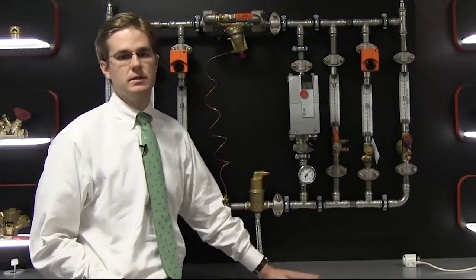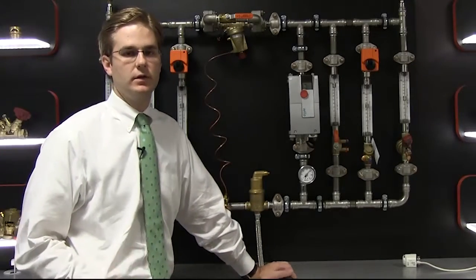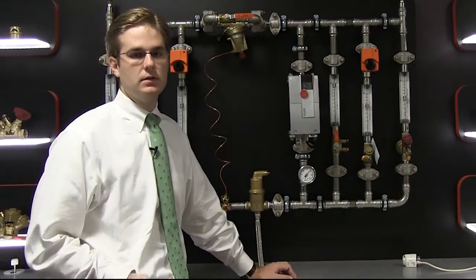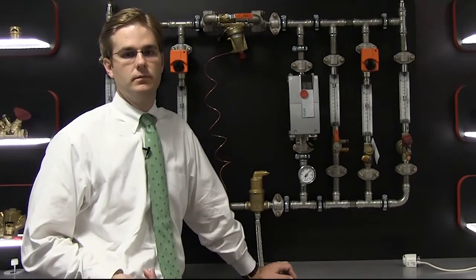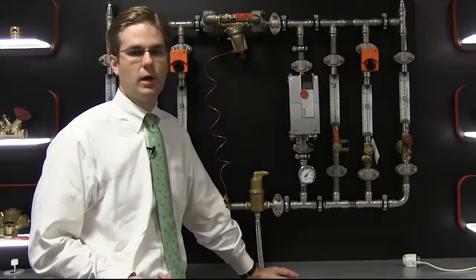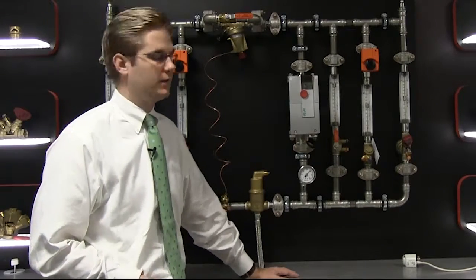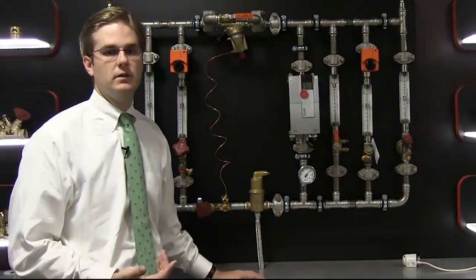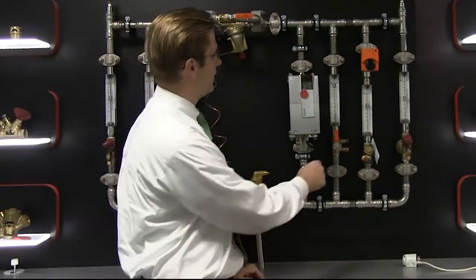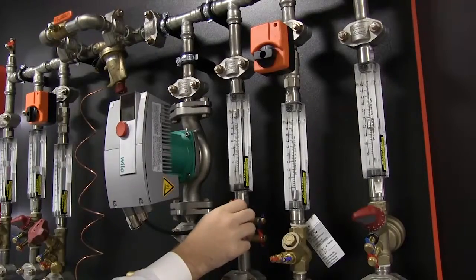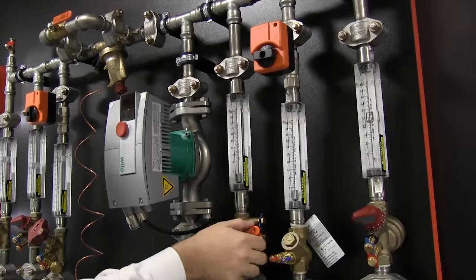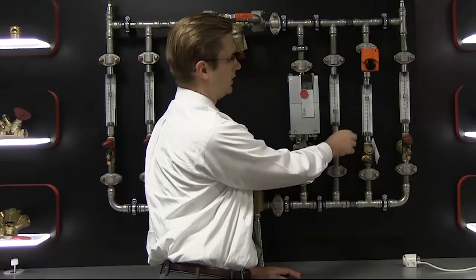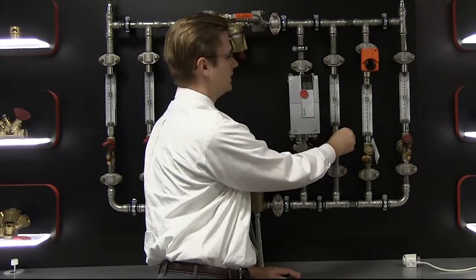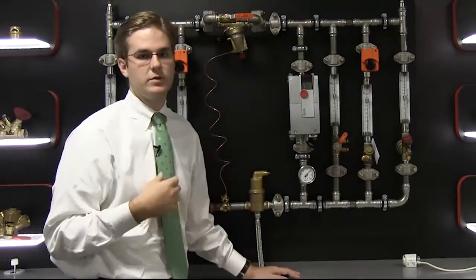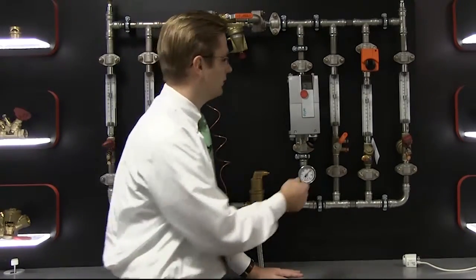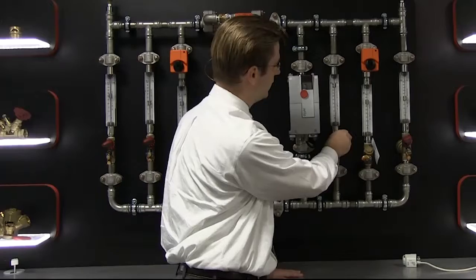Proportional balancing is getting enough flow at each terminal unit when the building is commissioned to achieve comfort at each room and to maintain proper room temperature at all times. There's a couple ways to do that. The first way is by using a quarter turn ball valve as a balancing valve. Because there's only 90 degrees to open, it may be difficult to get the proper set point that you want and get the proper flow that you actually want.